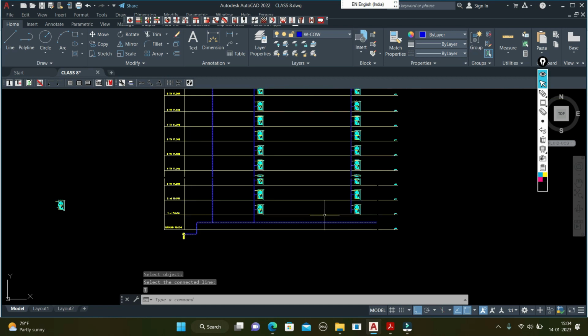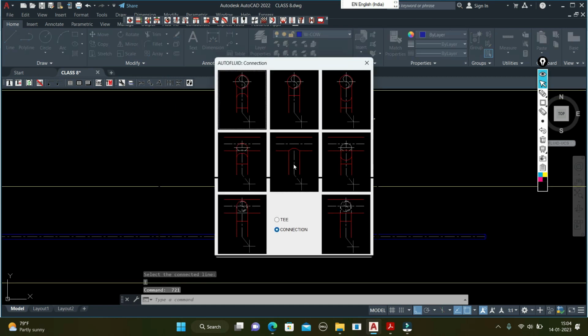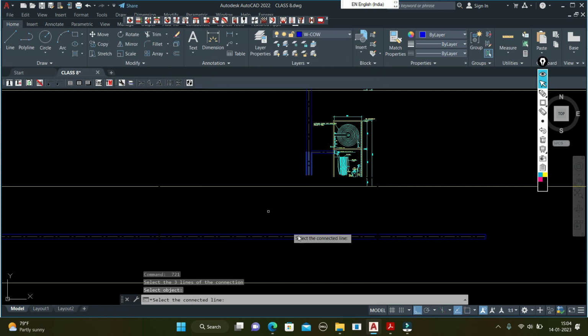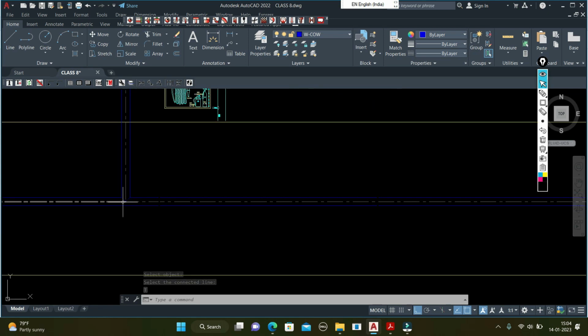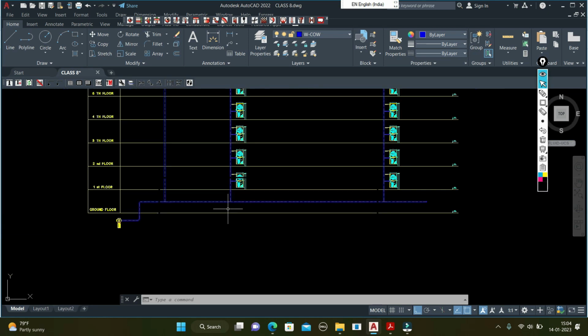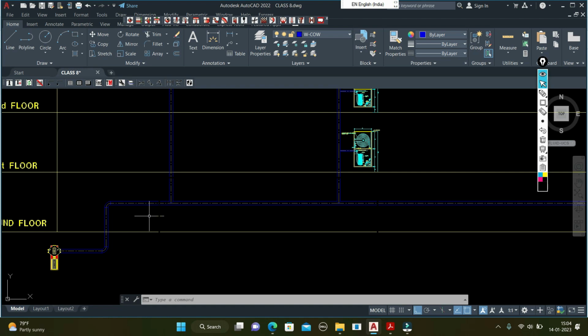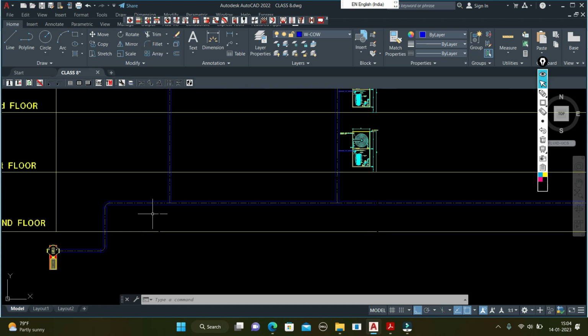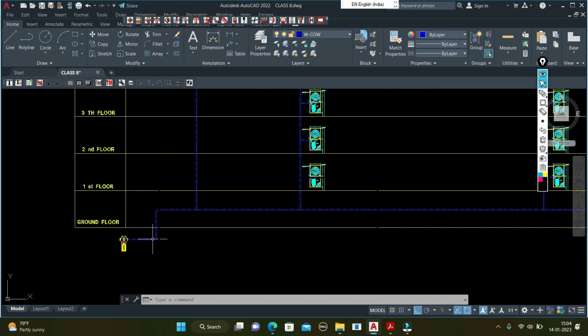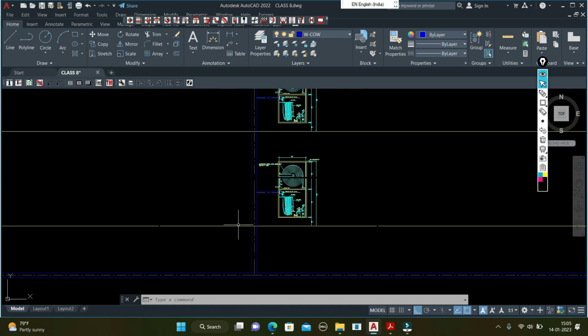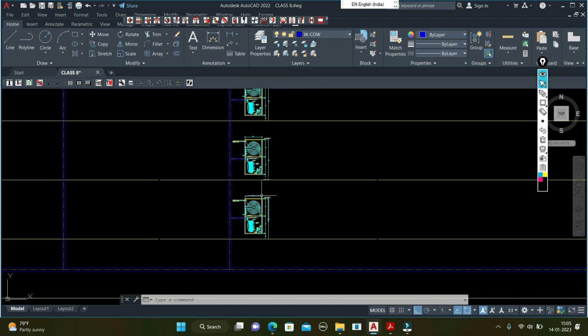It's connecting. Also take that one. Okay, now it's taking the branch. Okay, all this one is the 6 inch. Okay, but don't be confused about the pipe sizing. We will do a hydraulic calculation and size the pipe. But generally it's a rule that if there are more than 2 landing valves, we take the riser as 4 inch.